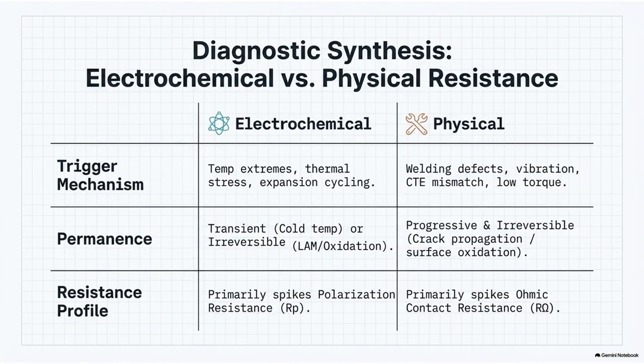When you compress two copper bus bars together with a hard steel bolt, you are dealing with different material stiffness and, again, those thermal expansion rates. Over years of thermal cycling, the copper literally creeps and relaxes under the compressive load of the steel bolt. The copper actually yields over time. It just gives way, reducing the clamping force. Yes. The initial preload torque that was perfectly applied at the factory just drops, and once the clamping pressure falls below a critical threshold, the joint is compromised. The connection gets loose. And it's not just a loss of physical contact. When the joint relaxes, it allows ambient humidity and oxygen from the air to penetrate the interface between the two bus bars.